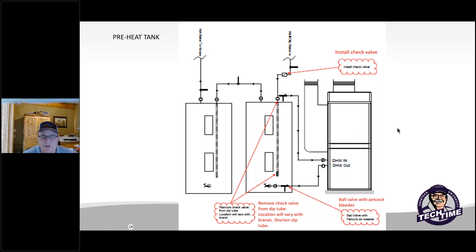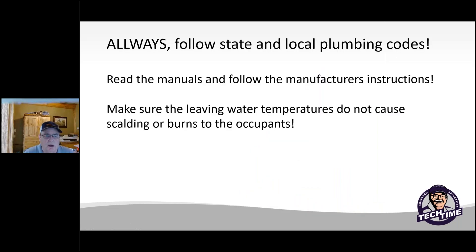Rules of the trade: always follow the state local plumbing codes. Read your manuals, follow some manufacturers' instructions to your specification which you like. But most of all, make sure this leaving water temperature does not cause scalding or burns to the occupants. 140 degree water, 150 degree water can burn infants and kids. Pay attention to that installation, be safe with your practices, and keep up the good work out there. Thank you again for attending today.